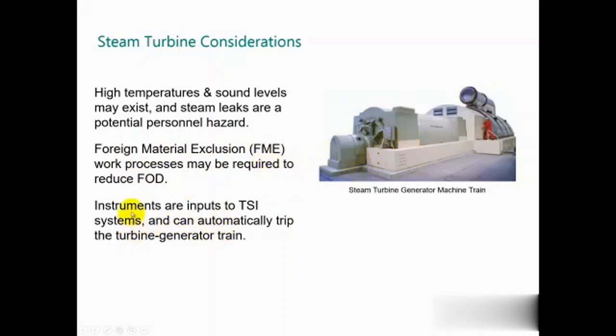In the steam turbine, all the instruments — especially in the big ones — are called the TSI, Turbine Supervisory Instrumentation. That includes vibration, differential expansion, eccentricity, shell expansion, thrust position, rotor position, and temperatures. This is all part of the TSI.